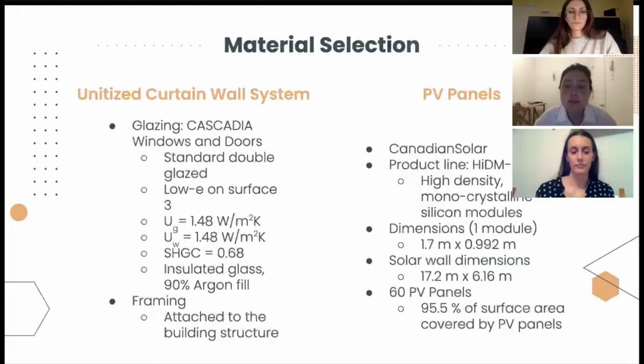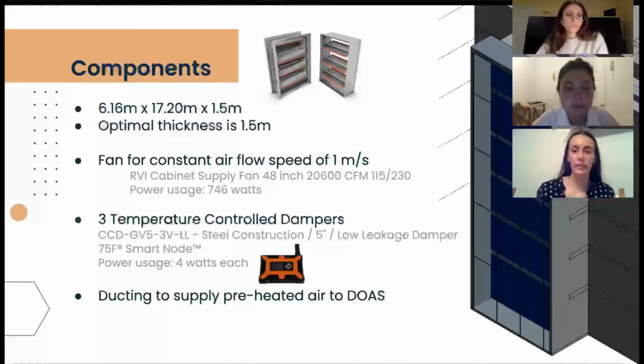In terms of the PV panels, this will be a Canadian manufacturer called Canadian Solar. The modules are monocrystalline silicon with a 19% efficiency, and each covers a surface area of approximately 1.67 square meters. From these dimensions, along with the dimensions of the solar wall itself, it was estimated that 60 units will be needed, covering just under 96% of the surface area of the solar wall. The solar wall spans the entire length of the stairwell and reaches a bit higher than the building's roof in order to connect the supply duct.